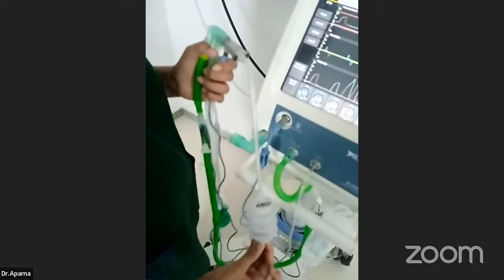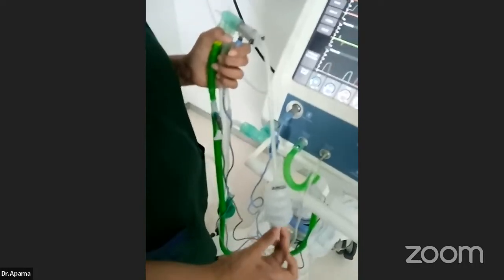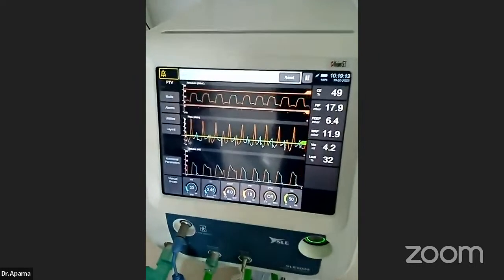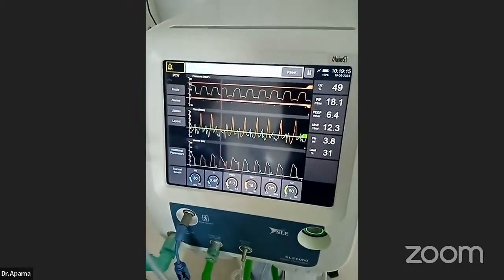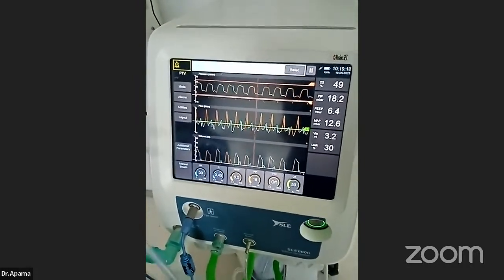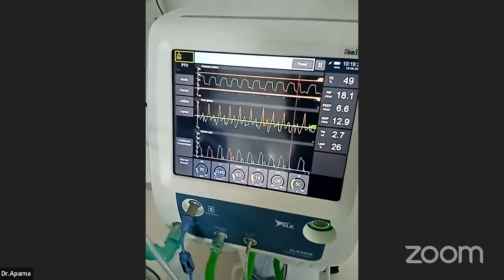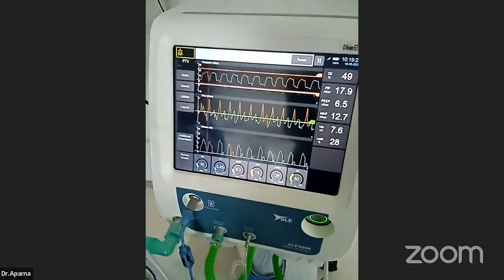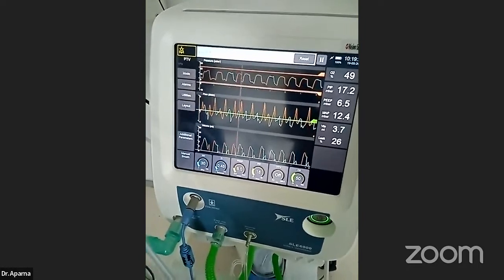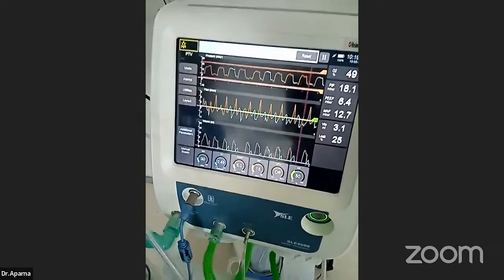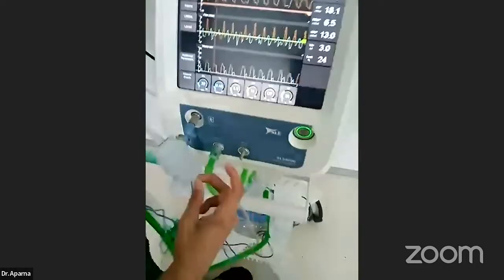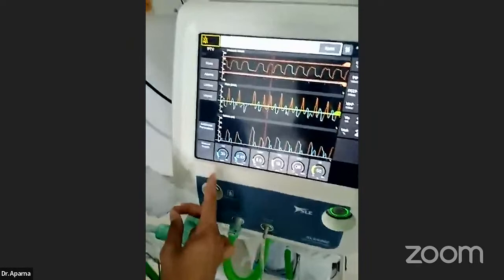Let's say we have a baby breathing at a fast respiratory rate. You can show the test now. So this is similar to the baby breathing. Now, because we have kept the baby on PTV, and PTV is the same as assist controlled ventilation, here we are not deciding the rate. The baby will be supported by any number of breaths that the baby initiates, provided the efforts are above the trigger threshold. Here we have kept a backup rate of only 30.